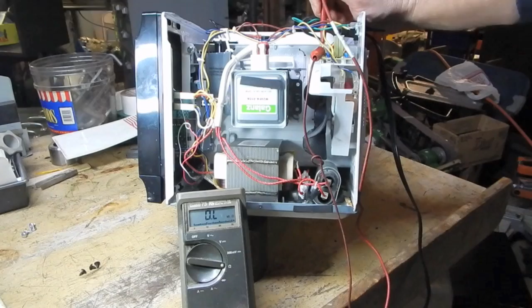And I see OL, which means out of limit. What I would rather have seen is 0.5 ohms, which is really just the resistance of these crappy meter leads coupled with the resistance of a bad connection. Oh look, it's getting better. So the fuse, she is cooked.